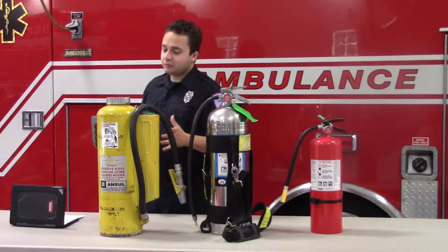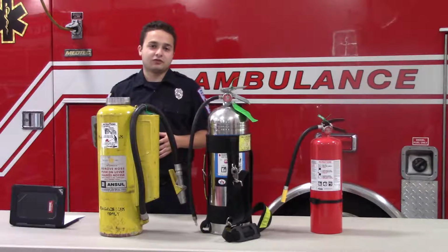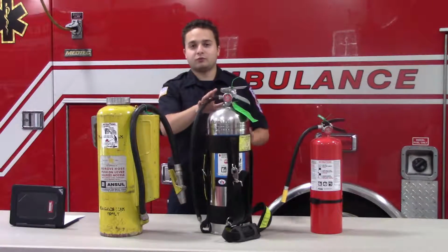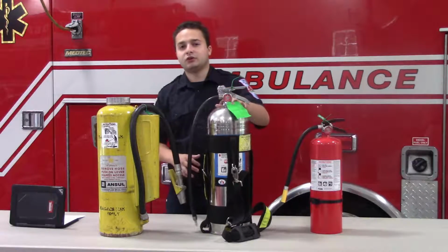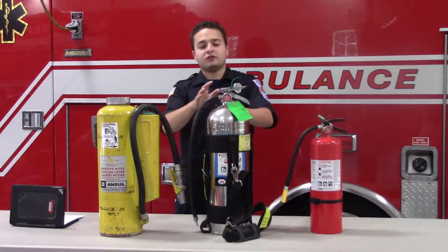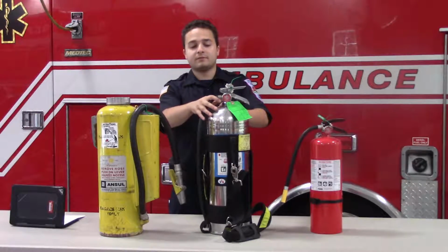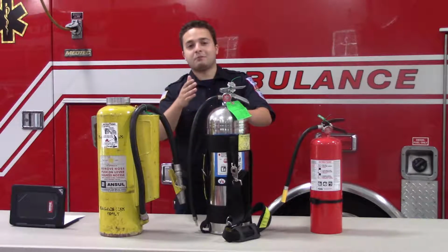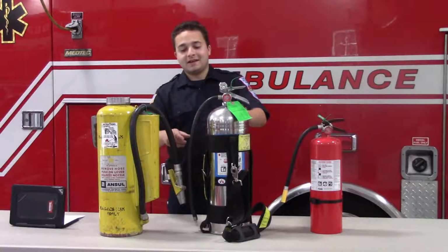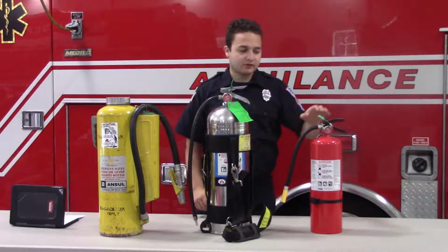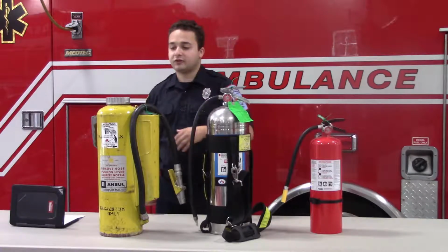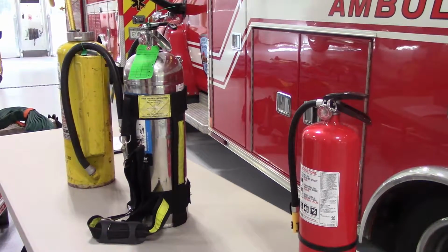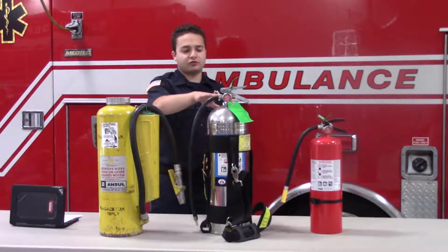In movies, you most typically see the carbon dioxide extinguishers versus a dry chemical. This dry chemical makes a very large mess. Water would be problematic, and you can't use water on every type of fire. It's only good on ordinary combustibles, like I said. You can't use it on flammable liquids because it could cause a much bigger problem. You can't use it on metal because it would cause the fire to get bigger, and it has a reaction to it. Dry chemical would be non-effective on metal fires, hence why we have a metal extinguisher. The one I'm not talking about is a Class K fire, which is cooking oils, and we don't have the extinguisher here.